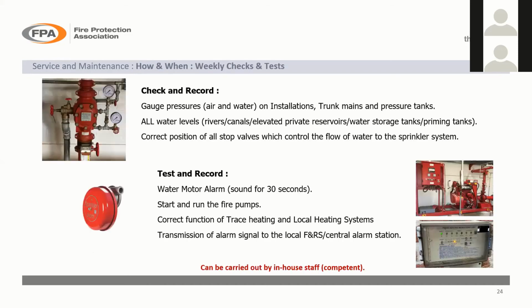So I'm just going to look at the checks now. We've listed them all out, weekly, monthly, quarterly, six monthly. Generally speaking, these are taken from TB203. Clause 20 is very, very similar, and if you apply the LPC rules, obviously TB203 supersedes the requirements of clause 20. But I do mention clause 20 because it is a standard in its own right, if you just choose to adopt that standard. From a weekly point of view, this is the in-house check.